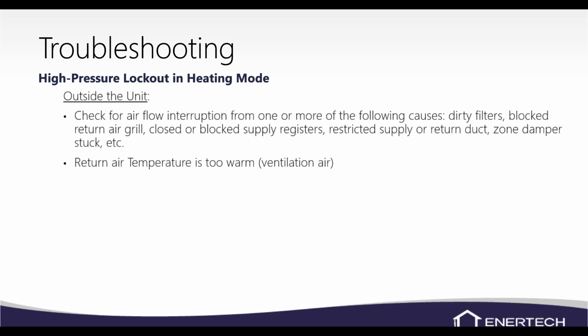Obviously, we want to look at your return air temperature. If for some reason it's too hot, you may want to check for some ventilation air issues, some ductwork problems there. Maybe you're getting too much bypassed on your zoning system, so you're overloading the unit with high return air temperatures.